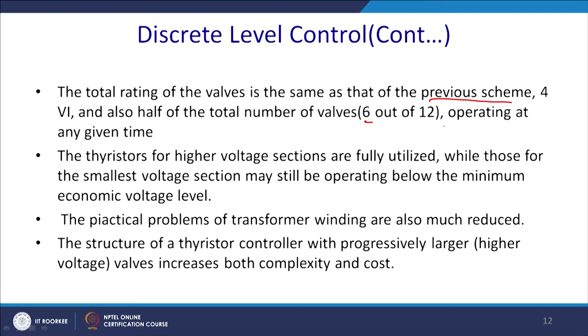Thyristors of the higher voltage sections are fully utilized, while those of the smallest sections may still operate below the minimum economic voltage level. The practical problem of the transformer winding is also reduced because you do not need that many leads to come out from your core.